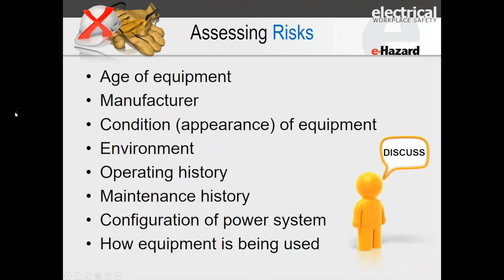And if it has not been maintained, if it's not in good shape, those questions, regardless of the direct contact shock issues or what a label and an incident energy analysis number comes up with, 7 calories per centimeter squared, answering these sets of questions, which is step two in a risk assessment, has major impact in regards to the personal protective equipment that you're going to select, and then certainly the job procedure and everything else. But so, are you ready to select your personal protective equipment after going through the assessment of risks?